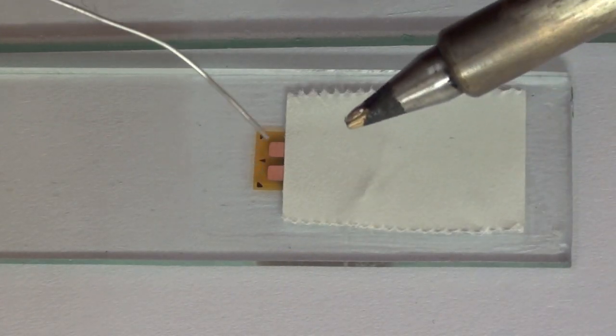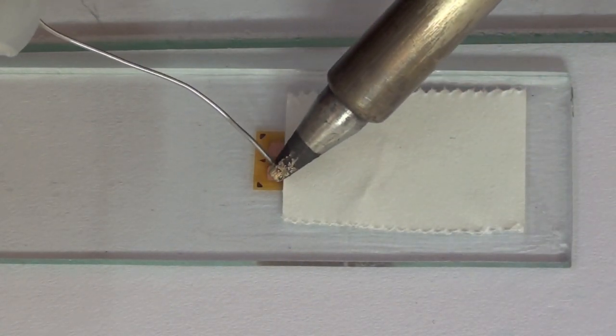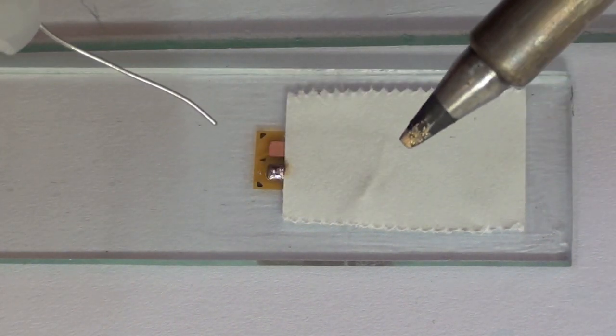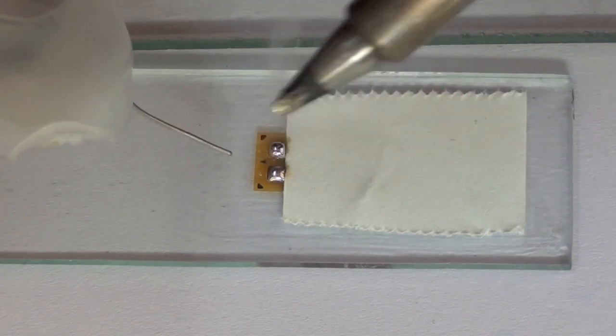The tabs of the strain gauge are also tinned with solder. The end of the solder wire is placed over the gauge tab, then touched with the tip of the soldering pencil and a small amount of solder is fed into the tab before lifting the pencil away.